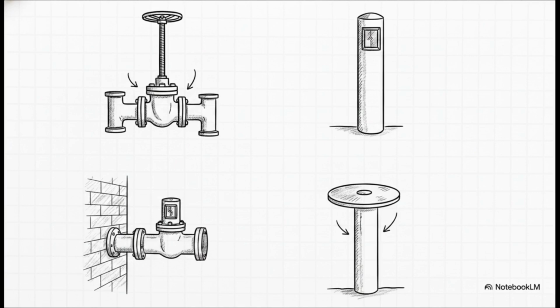First, the OS&Y, which stands for outside stem and yoke. It's super simple. If the threaded stem is visibly sticking out beyond the yoke, the valve is open. If the stem is invisible, it's tightly closed. Next up is the PIV, or post indicator valve. This is a hollow metal post sticking out of the ground with a small glass window that literally displays the words open or shut. You can't miss it. The WPIV is exactly the same concept, but it's a wall post indicator valve sticking horizontally right out of the building's exterior. Finally, the PIVA, or post indicator valve assembly. Instead of words, it uses a circular disc right on top. If the disc is perpendicular to the plate, water is flowing. If it's perfectly in line with the plate, the valve is shut.